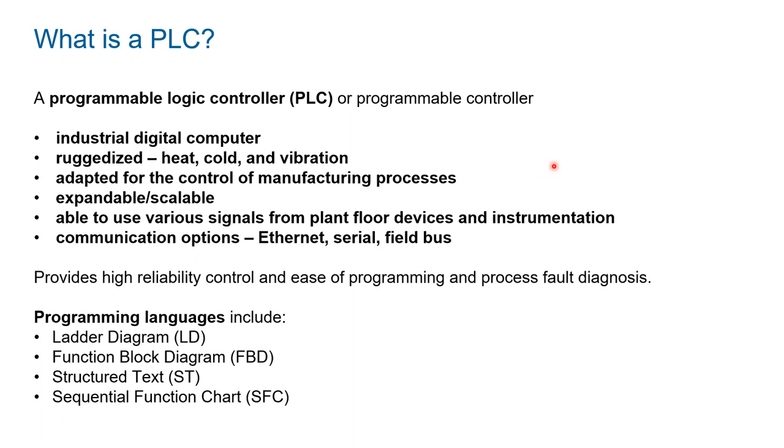Being that it's meant for industrial manufacturing, it's designed to take in the plant floor devices. I've seen many people say, well, can't we just use a Raspberry Pi, or an Arduino or something to do the same stuff? The answer is yes. But the problem is the Arduino is not designed to take 24 volt DC signals, or 120 volt AC input signals, or 4 to 20 milliamp signals. It's designed to take in like a 3 volt signal. So it's designed to be more electronic duty versus industrial pilot duty, they call that. It works in the same manner, but it's just not designed for the industrial world.